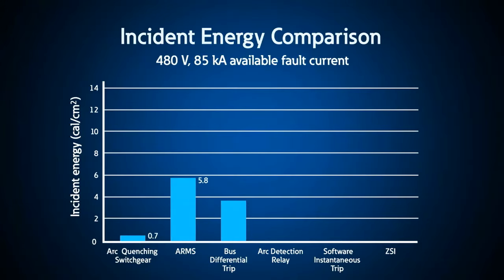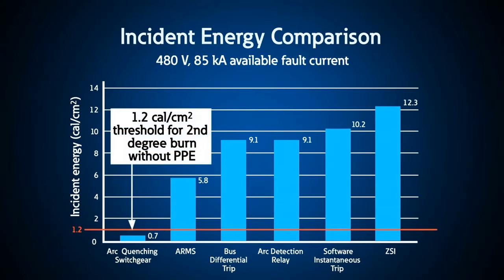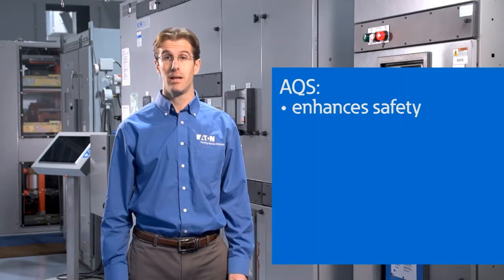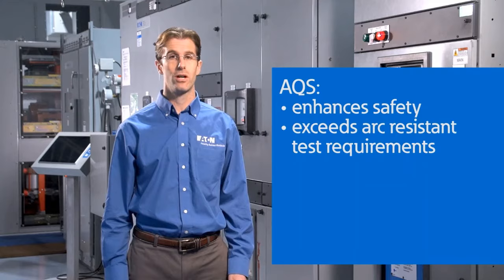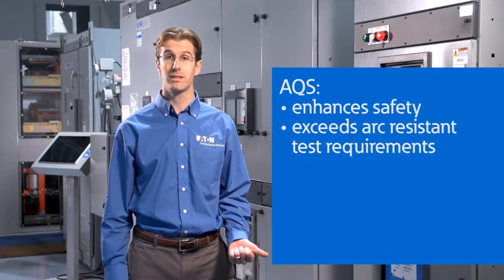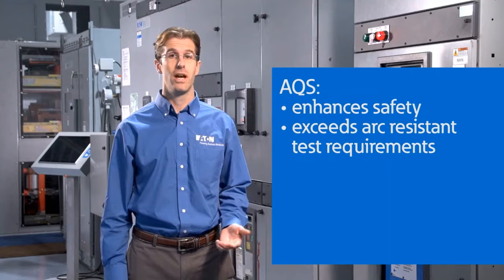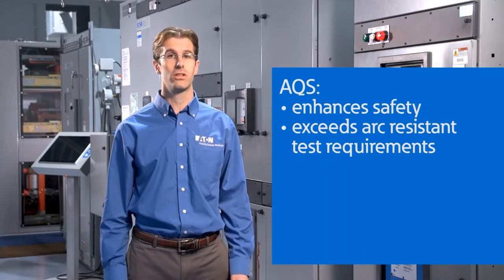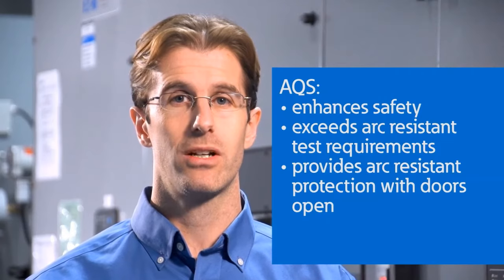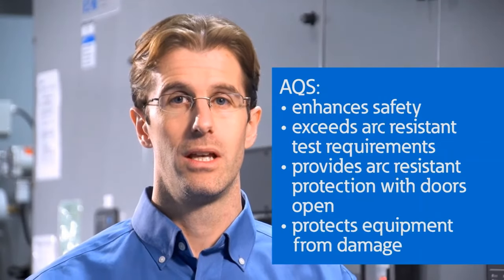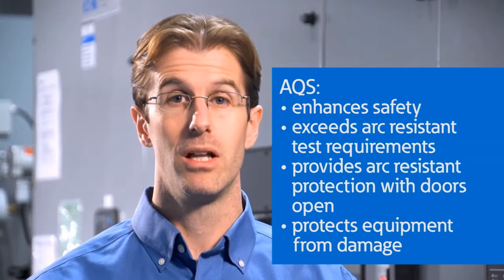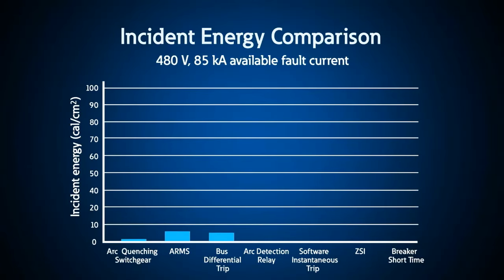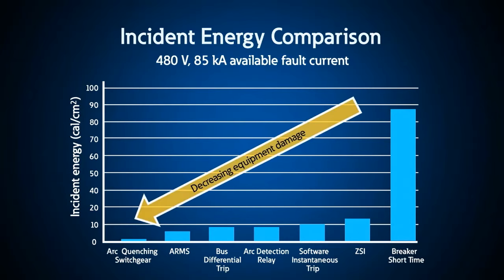In summary, Eaton's arc quenching switchgear is an incident energy reducing system. It can actually reduce the incident energy to less than 1.2 calories per centimeter squared. So this enhances safety, it enables the switchgear to exceed the arc resistant test requirements in standard construction without the need for ducts, plenums, thicker gauge steel, and the special construction that you normally expect with arc resistant equipment. And it even provides arc resistant protection when the doors are open or panels are removed. It also protects the equipment itself from damage, unlike arc-resistant equipment, where the internals can be destroyed. And since it protects the equipment from damage, it can dramatically reduce downtime in the event of an arc flash.